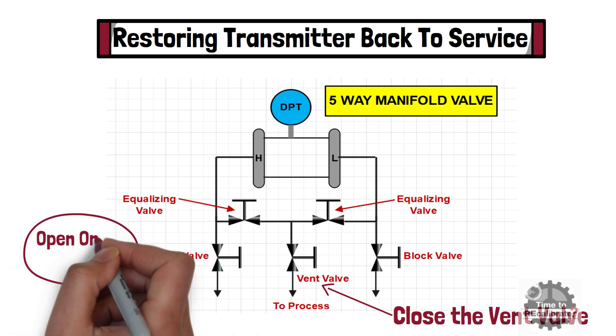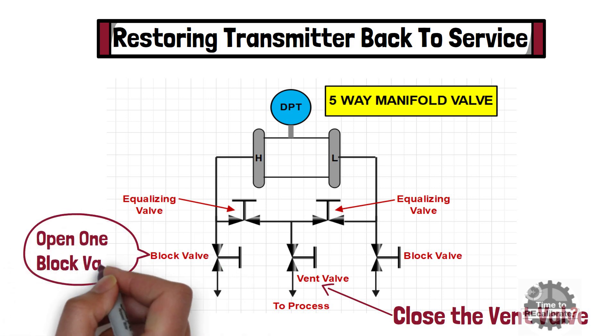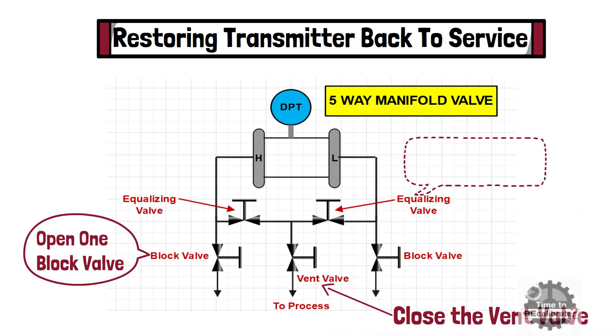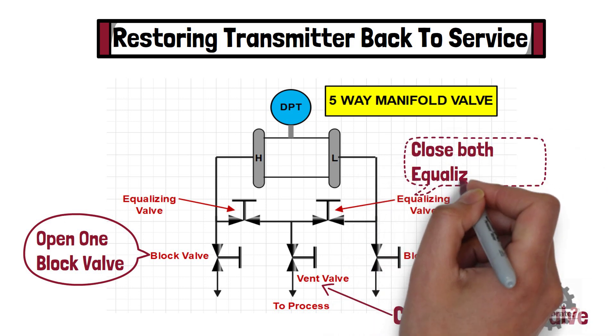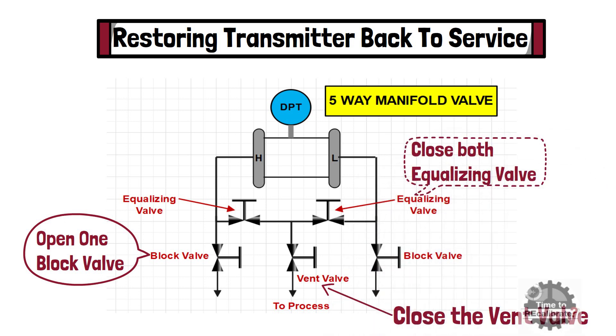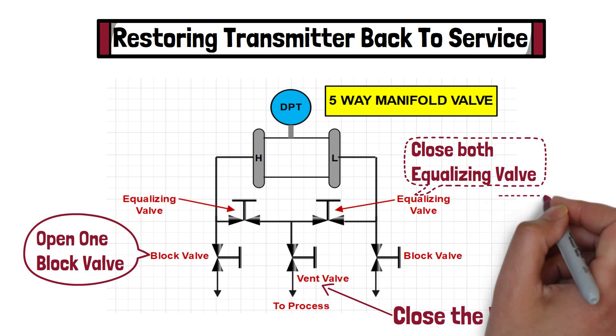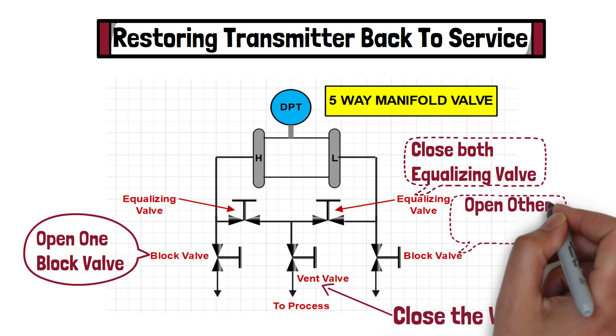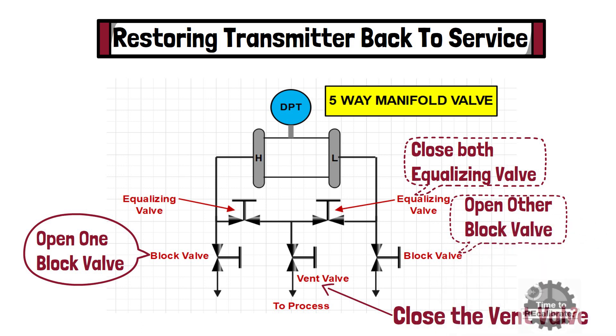Then open one of the block valves. After this, close both equalizing valves — which one does not matter. At the end, open the other side block valve. Once we open the other side block valve, the DPT is in service and it will show the differential pressure reading on the display.